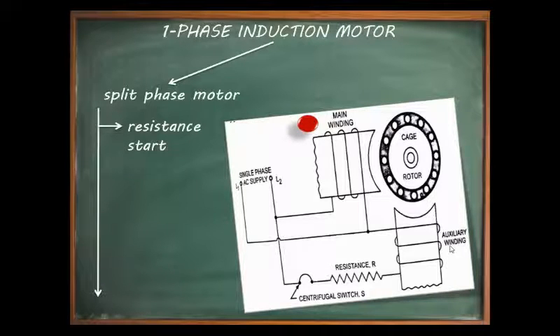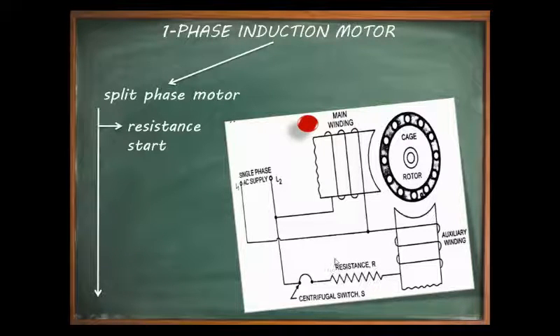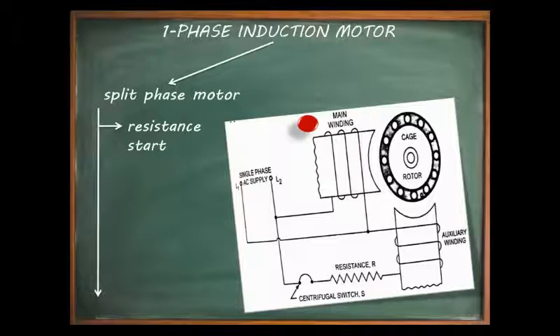In this type of motor an extra resistance is added in series with the auxiliary winding, creating a phase split between the two windings — hence it is called the resistance start single phase induction motor. After the motor acquires 75% speed, the centrifugal switch as shown in the figure opens and the auxiliary winding is cut off from the main winding.